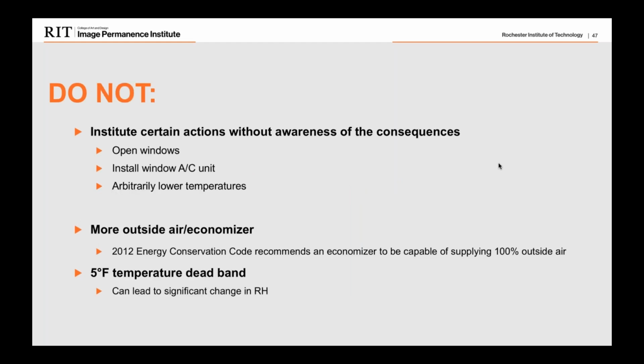And then there are other things that we want to make sure to avoid. We've talked a little bit about this throughout the webinar, but certainly lowering temperatures, either through set point changes or through window AC units—if we don't have an understanding of how that might affect relative humidity levels through the dew point, this can cause problems later on. We looked at examples of the risk of mold germination and accelerated metal corrosion and all of those things. So we want to make sure that if we do lower temperatures, we have a sense of how that's going to play through the dew point and impact the relative humidity as well.